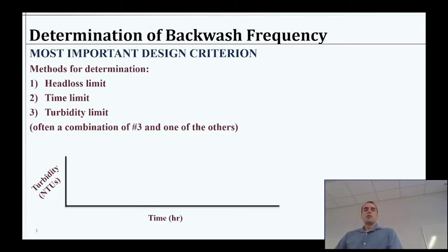and then they're backwashed into a wastewater stream. So what we want to do in terms of math is figure out a robust way to describe how often we need to backwash and how to account for that amount of water, so that we know how many filters we need in a plant, given how quickly we can add water to them and given their dimensions. Basically we need some math that shows us how to deal with filters that have to come offline and waste some of the water we produced when we do so. So that's the issue here.